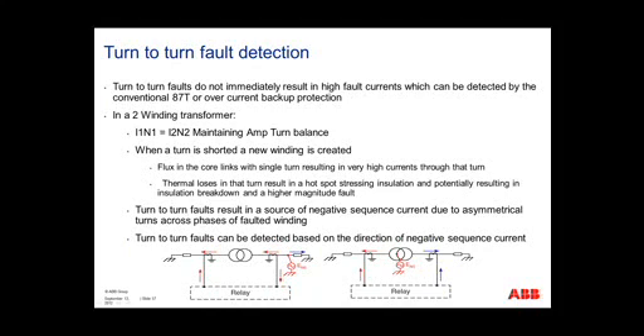This question actually goes back to one that you previously answered. It's asking, why is an external secondary phase-to-phase fault the worst case scenario? Because you're going to see the most current going through a three-phase fault. The worst kind of fault is a three-phase fault, and that's where you're going to see the most damage because of the most current flow inside of a three-phase fault.